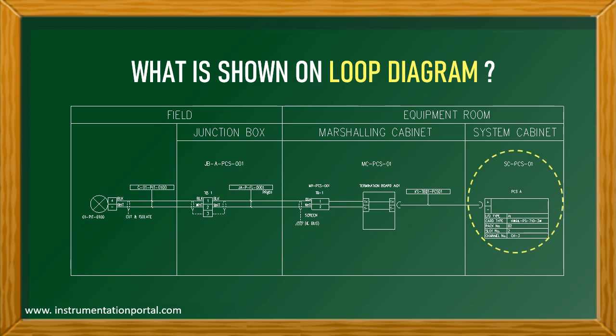Control system details such as controller number, IO type, rack number, slot number, and IO channel. Loop diagram also clearly indicates the location of each equipment by means of borderline as a limit.